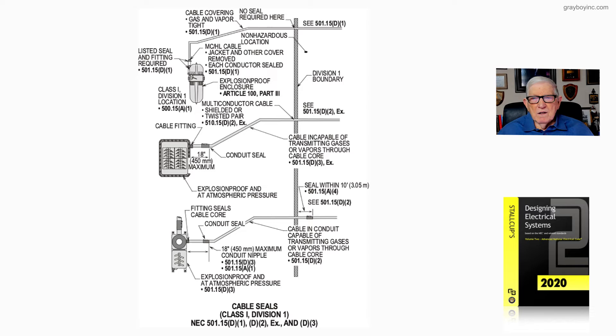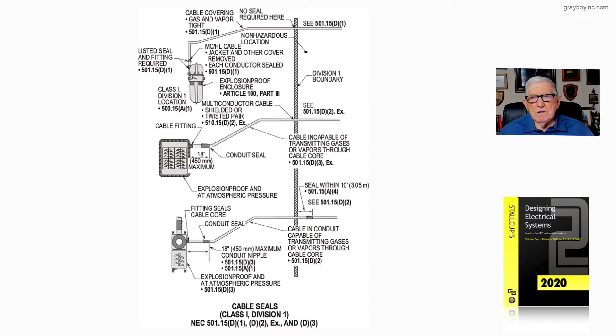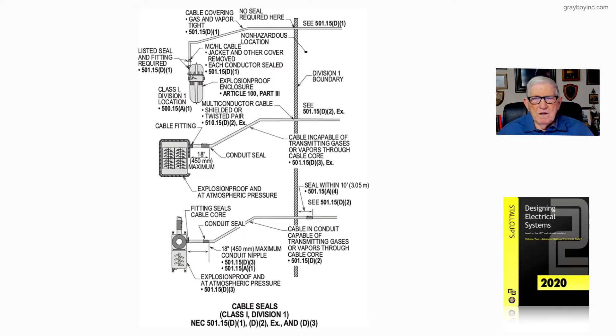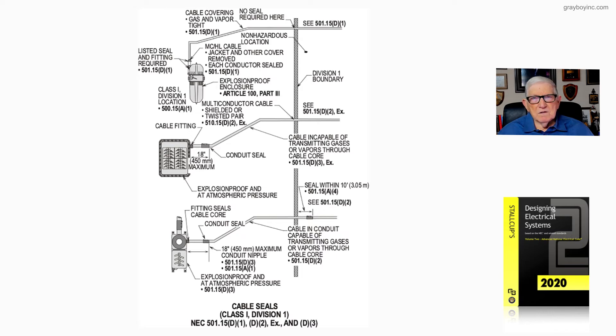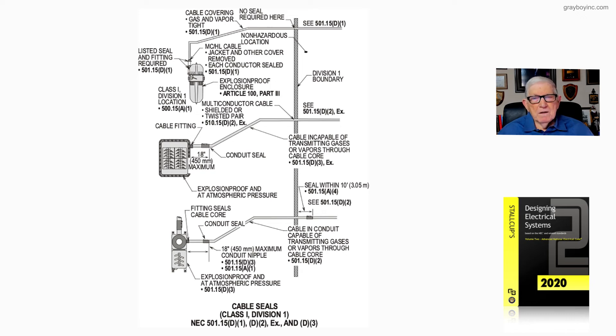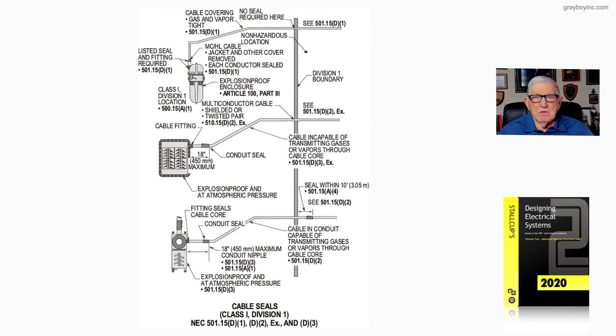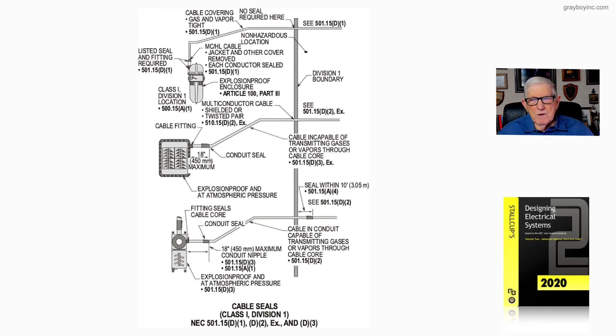This bottom illustration shows we seal within 10 feet of the boundary in accordance with 501.15a4 and 501.15d2. Then notice we would seal around that core. We'd have to use a fitting around the cable that would fill the core so that we wouldn't pass the vapor through the core of the cable. The raceway system is sealing around the cable so it wouldn't pass through the conduit system.